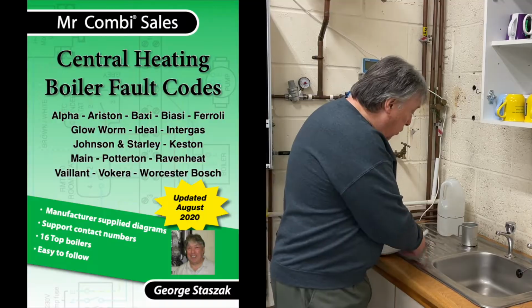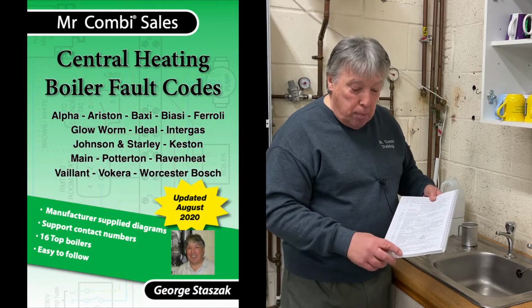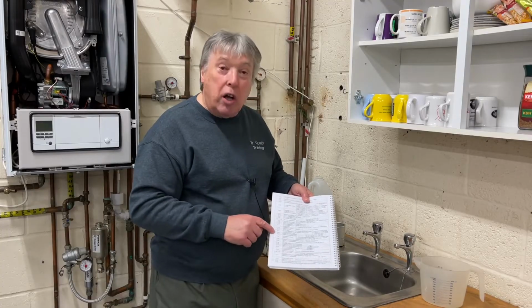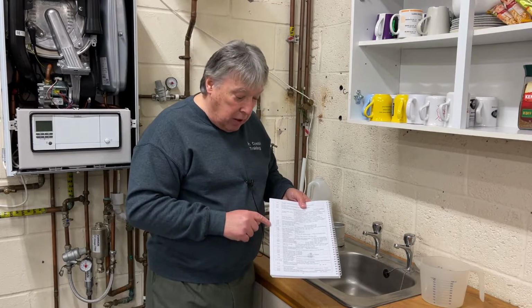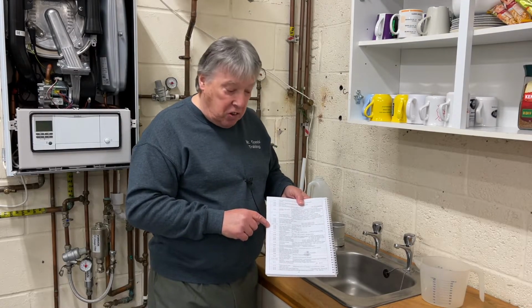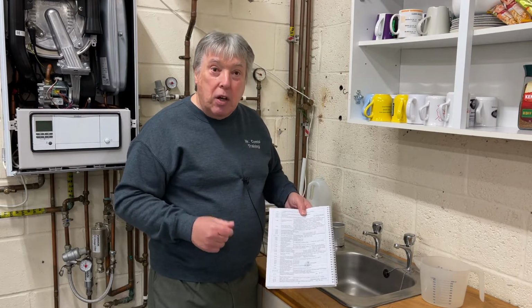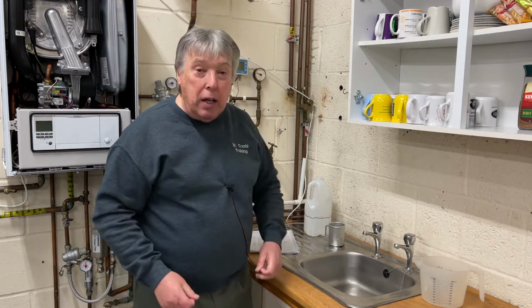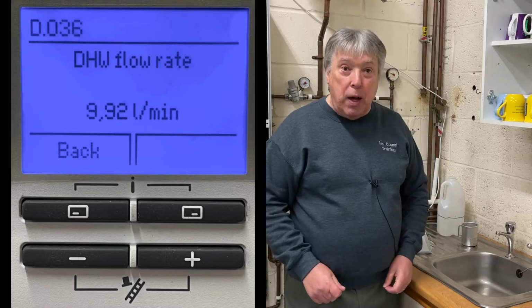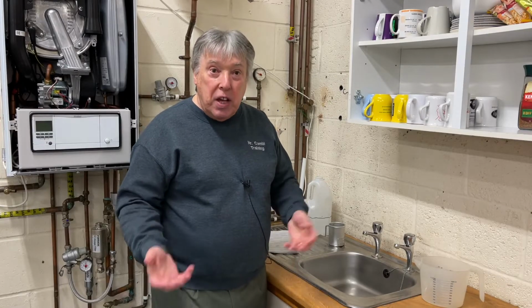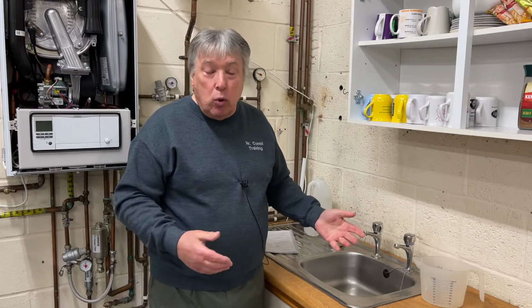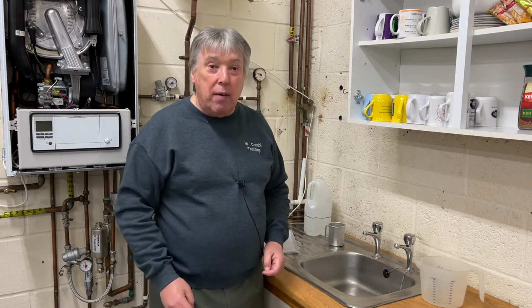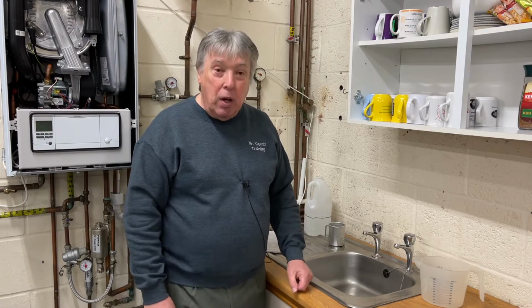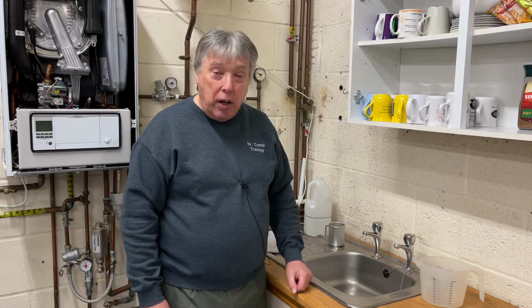And in our green fault codes book on page 56, where we go into Diagnostics, which is the upper level, D36 gives us the litres per minute that's actually going through the boiler, and then I'll show you a picture of that display and proves that it is 10 litres or 11 or 12, whatever it is. That'll tell us that we have the right and the correct flow rate, and the aqua sensor is working fine. If it isn't, I'll show you how to actually measure it using volts DC and hertz.